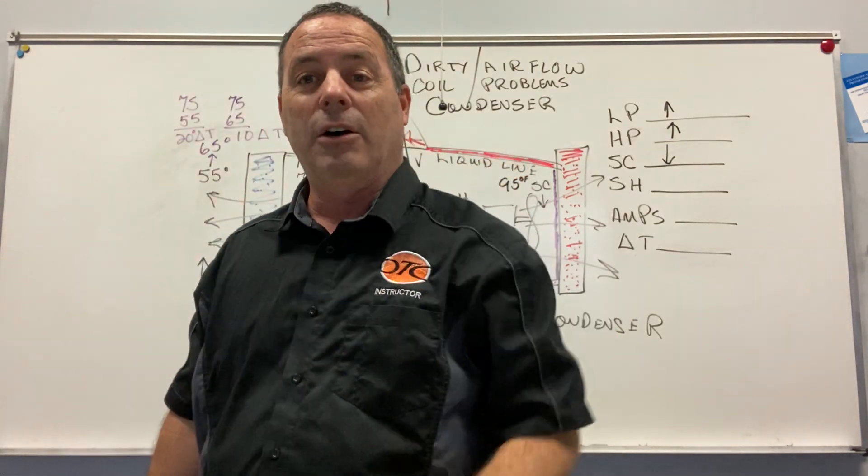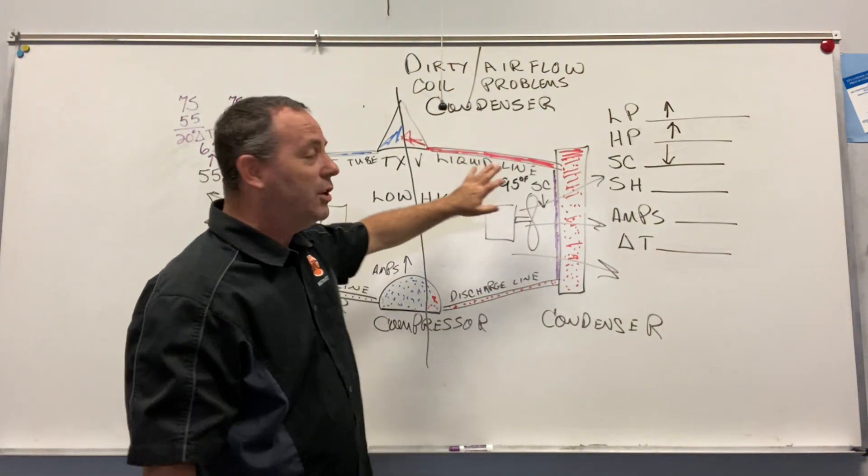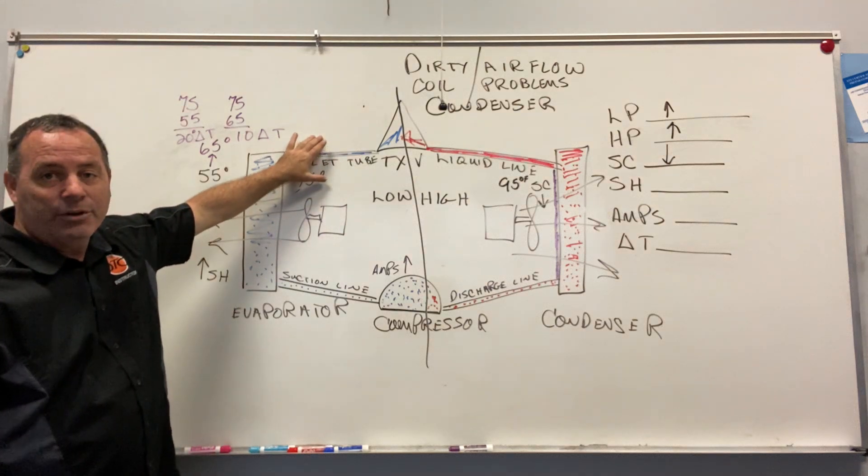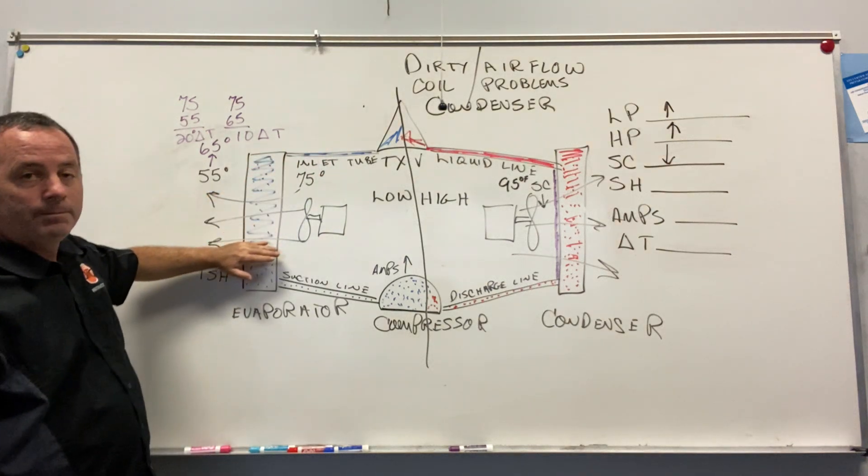Your liquid line will be hotter. When they get a real dirty coil, it might be hot to the touch. So that might be hot. Now, of course, you're going to have more heat entering your evaporator coil. So your coil is going to boil off faster and have increased superheat.